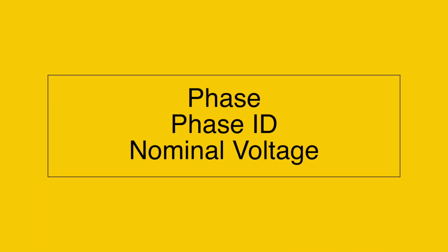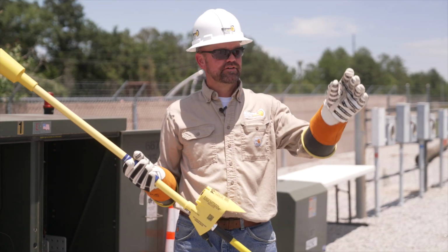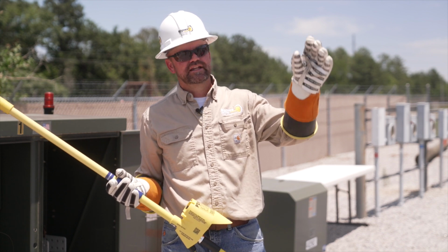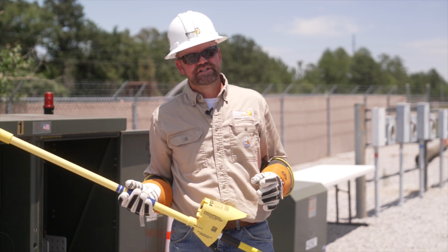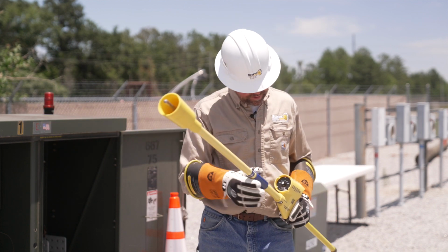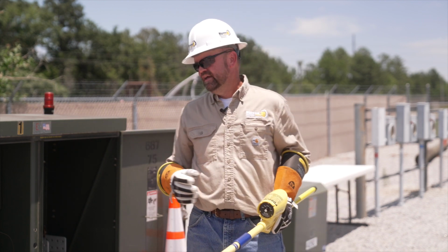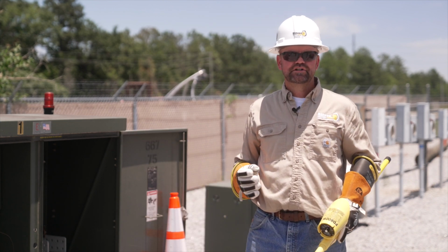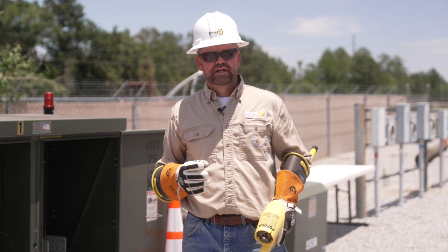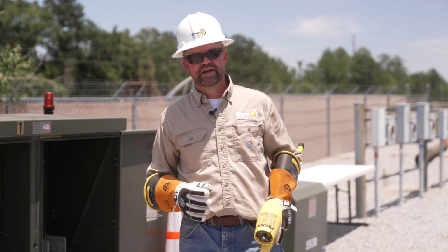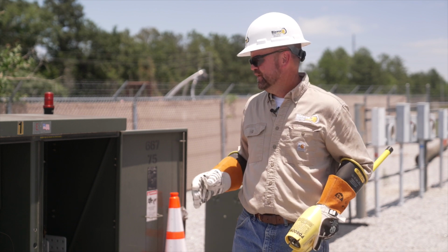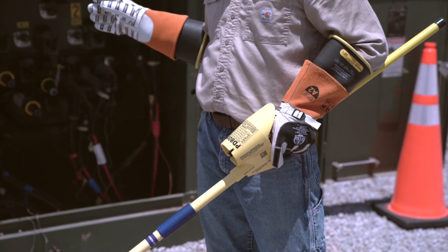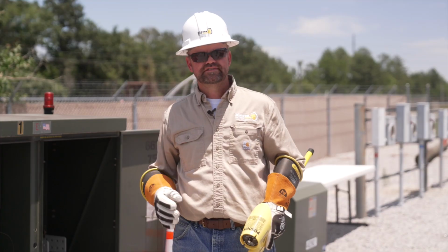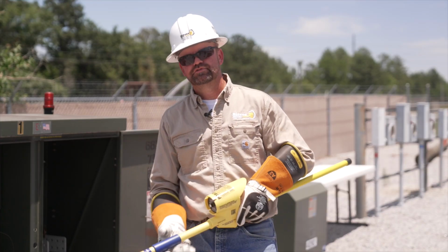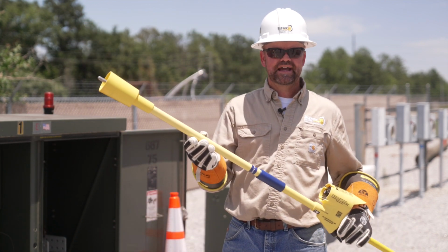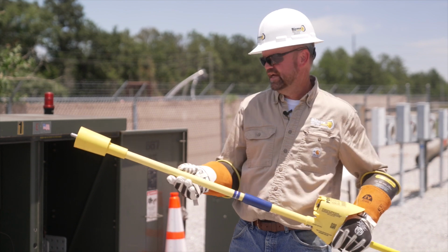So in this demonstration, I have our reference probe hanging from our overhead conductors behind us. Again, it's about 50 feet away. I have it in the DEG switch position. And on my meter probe, I'm going to put it in the URD switch position. And in each one of these bushings, I'm basically going to do 3 things simultaneous. That's a very unique feature with this tool. I believe it's the only tool manufactured that can perform this function, where I'm going to phase sequence and take a nominal voltage reading all at the same time. So again, I can start on any one of the 3 bushings. I have my 0 ohm extension attached to my meter probe, so I'm going to get a much more accurate reading when I do this.